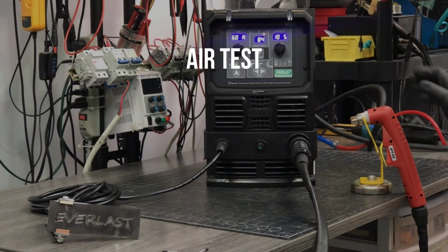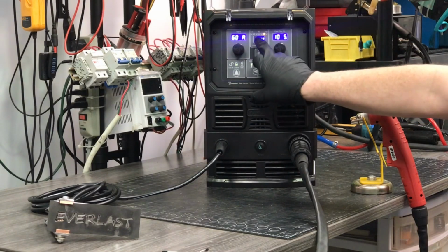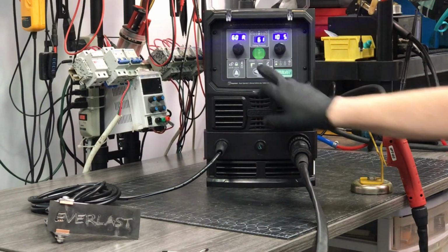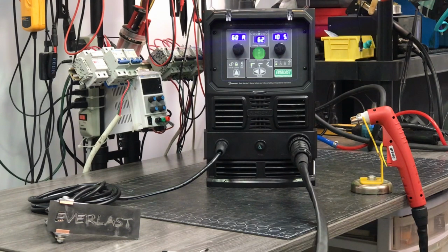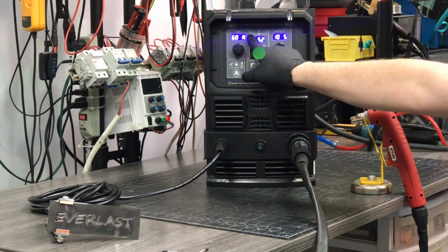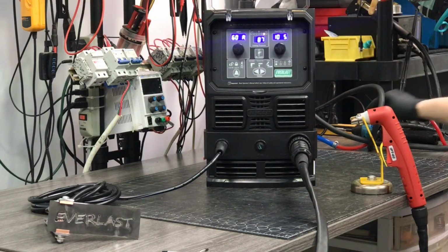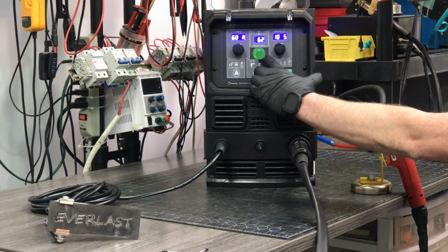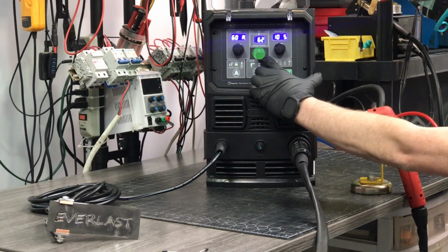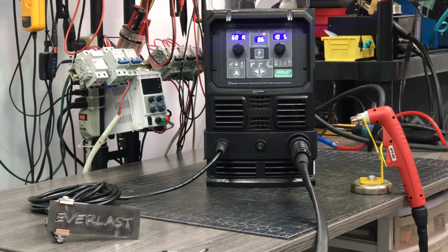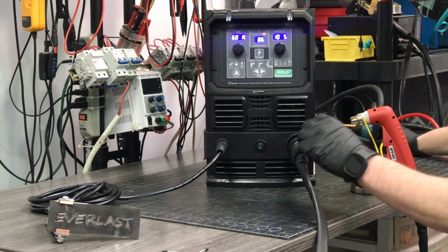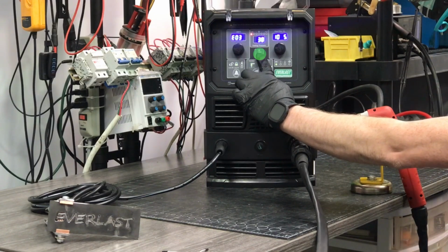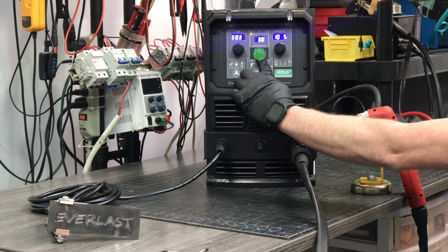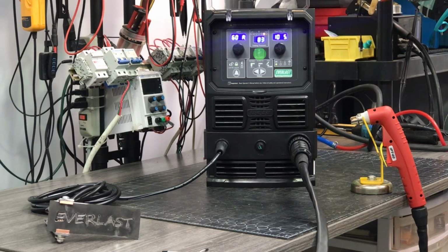Now we're going to check for issues with the air system. Start by selecting the air check button to confirm air flow, check for leaks, and make sure the air pressure does not drop more than 15 psi from the static displayed air pressure. Then we're going to cycle the air check on and off while making sure that the air turns on and off with the LED indicator. This will help us identify a solenoid issue or a CFM volume issue. Because the E03 code for PSI too high or too low is a non-latching error code, we'll be looking to see if the air check LED stays illuminated while no air is flowing.